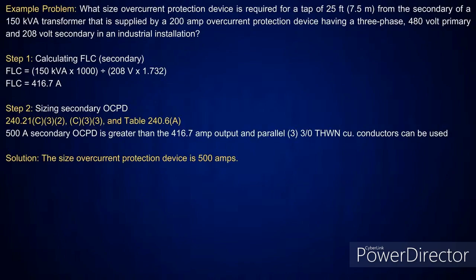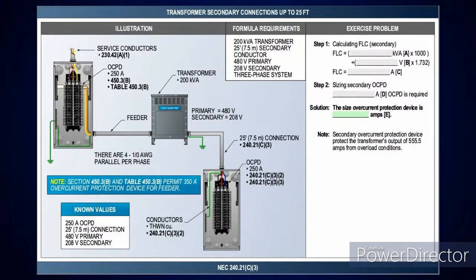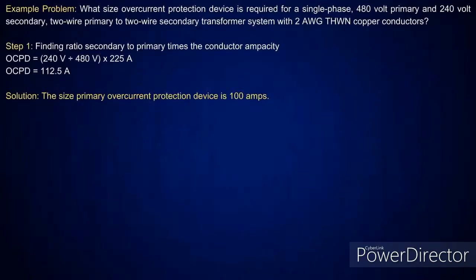Same thing here. We've got a 250 amp overcurrent device upstream. And then what's my secondary? It's 208 volts. So I'm going to take the 360, divide it into the transformer, which is 200 kVA, get my amperage, and then I size my overcurrent protection device. Okay, and that'll be homework for next week.